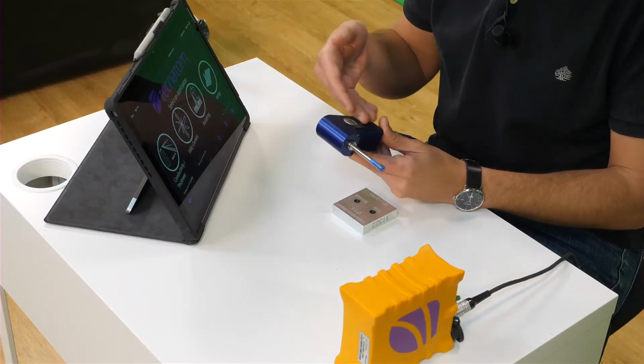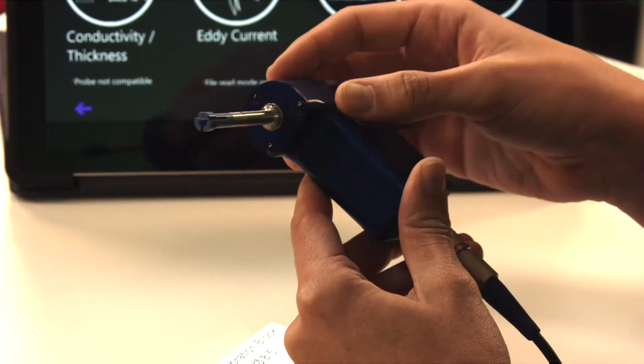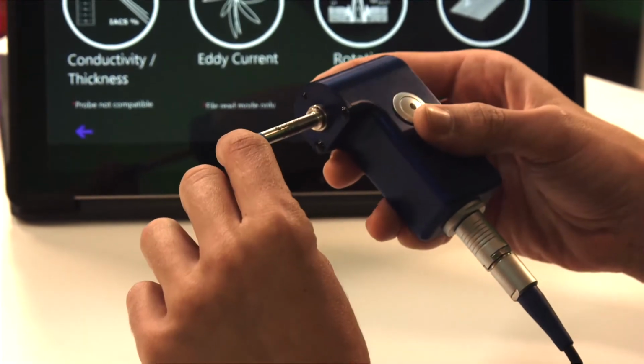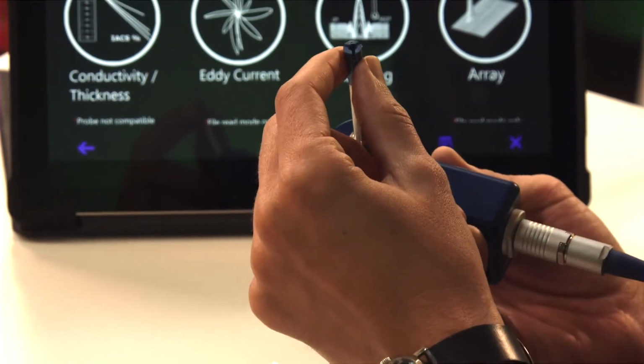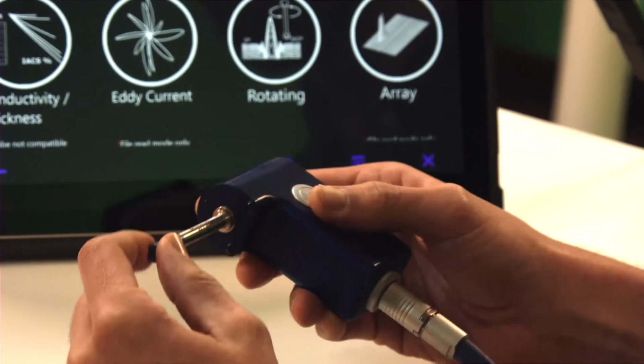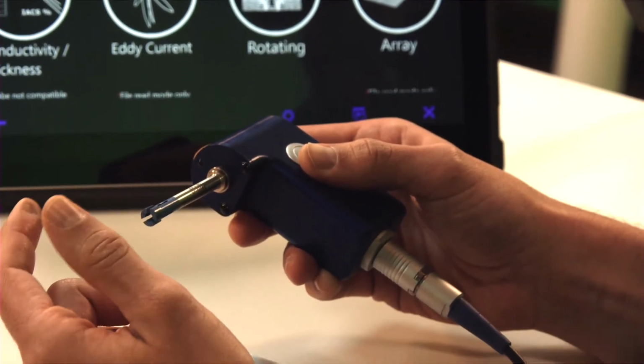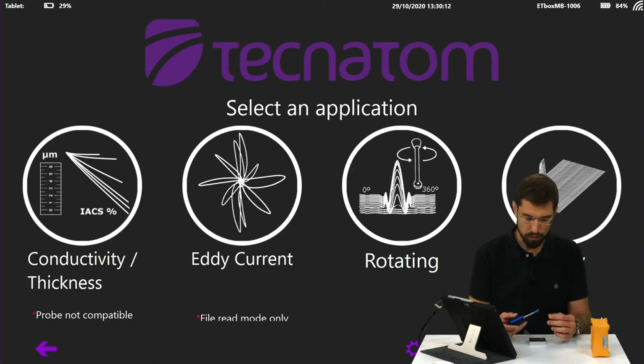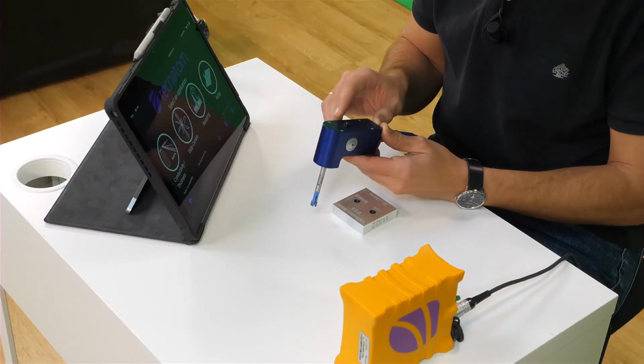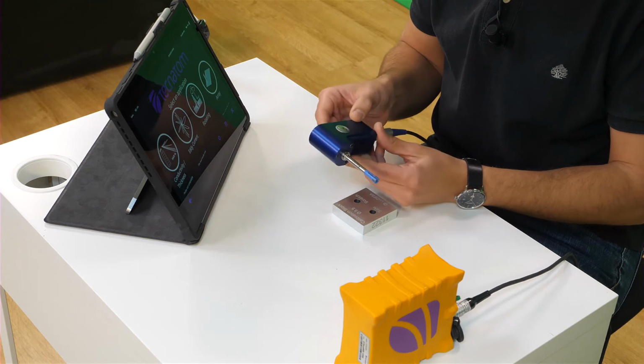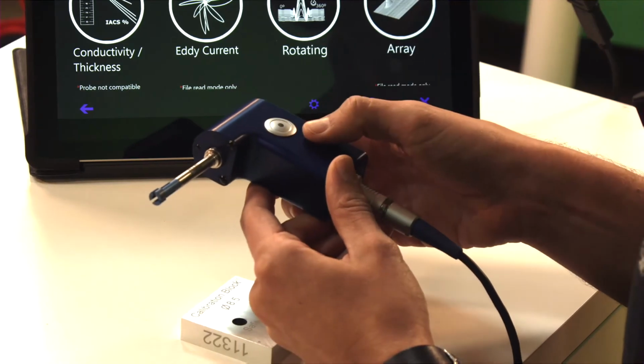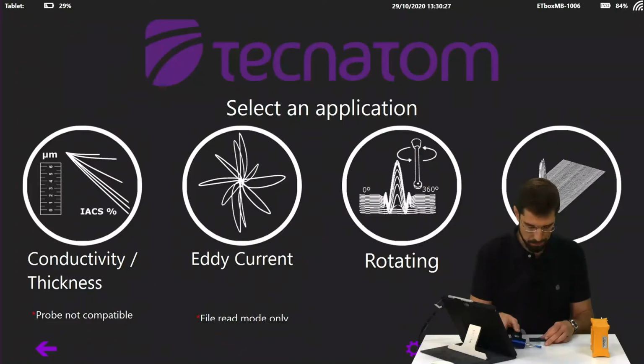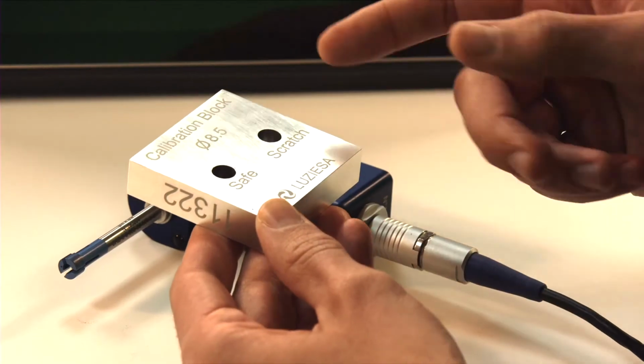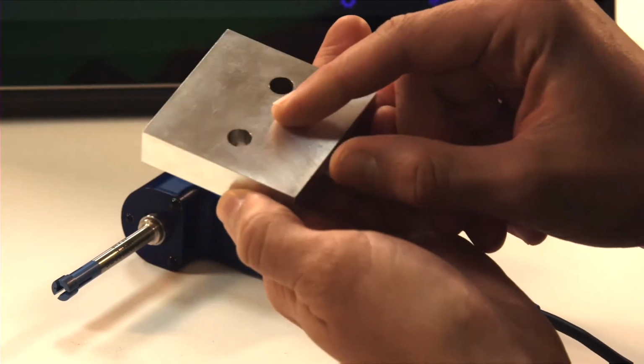As you can see, the probe has a body inside, which is the motor, as well as a rod with a coil. In this case, it's prepared to do an inspection of bores with diameters between 8 and 9 millimeters. But we could change it for a different one depending on whether we need a larger or smaller diameter. We can also see that the probe has an LED that lights up when an alarm goes off, and a switch to activate and deactivate the rotation. In this demonstration, we will make use of this calibration block that has 2 holes, one of them with indications and the other with a crack, as we can see in this image.